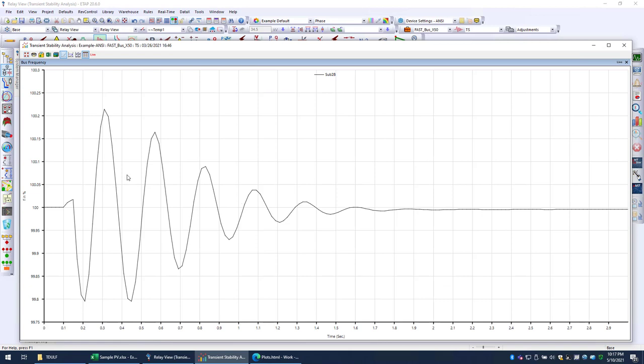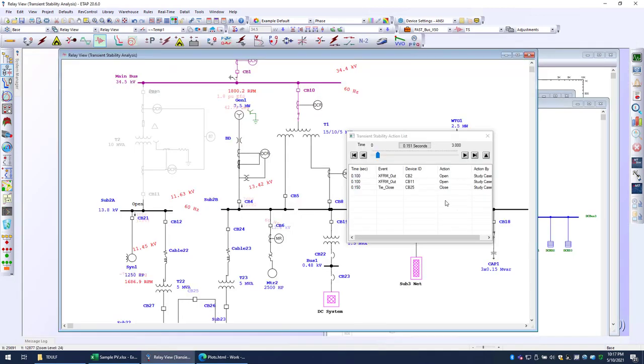And we can see here that it actually never went above a quarter of a percent on the frequency. So although we can see here the effect that particular fast bus transfer had, it had no impact on activating my load shedding. So it's a very professional way to verify load shedding settings.